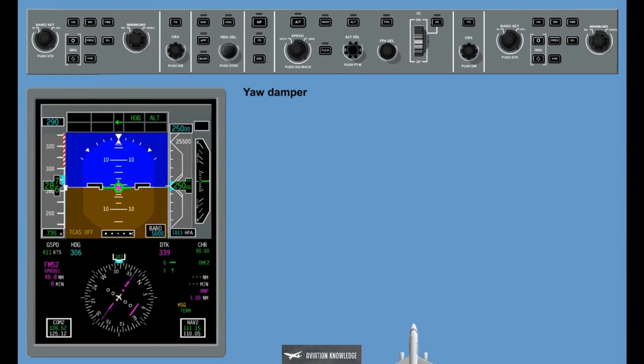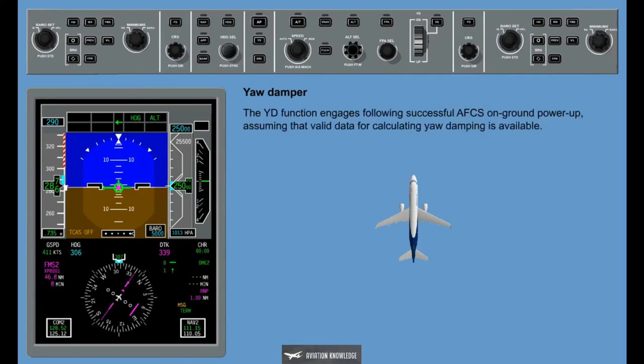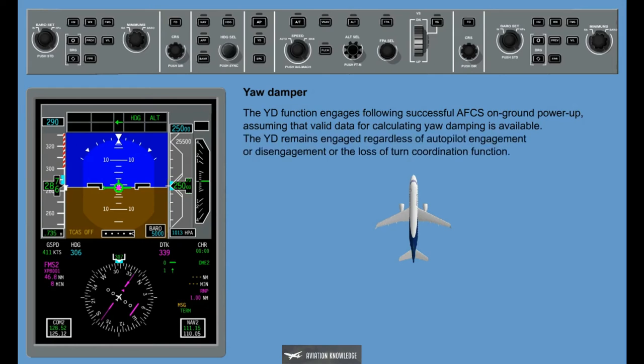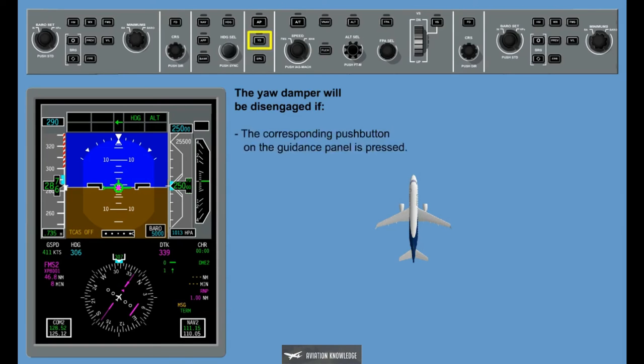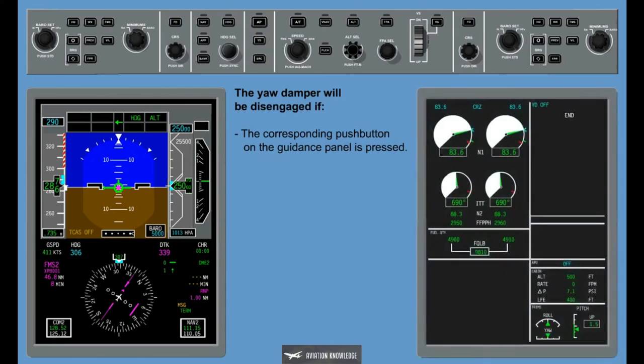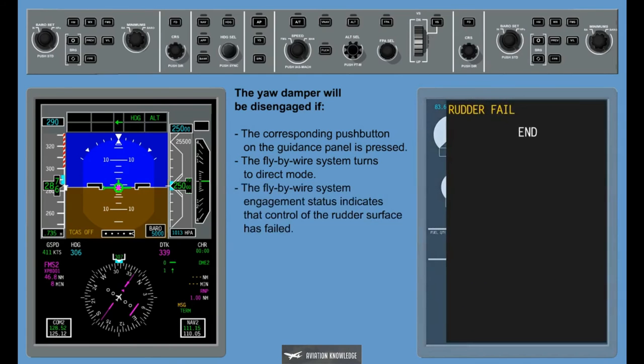The Yaw Damper provides commands to the rudder control surface and actuates it independently of the autopilot and flight director system. The yaw damper function engages following successful AFCS on-ground power-up, assuming that valid data for calculating yaw damping is available. The yaw damper remains engaged regardless of autopilot engagement or disengagement, or the loss of turn coordination function. The yaw damper will be disengaged if: the corresponding push button on the guidance panel is pressed (in this case a yaw damper off message will be displayed on the CAS window); the fly-by-wire system turns to direct mode; or the fly-by-wire system engagement status indicates that control of the rudder surface has failed.